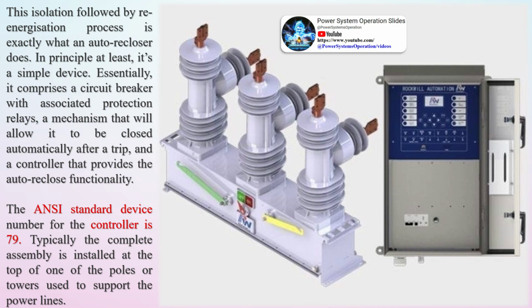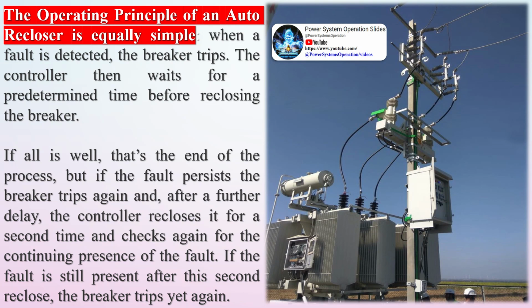If during this time a trip occurs again, the second cycle of the auto-recloser will run in case of multiple shots, or the first cycle will be completed as unsuccessful, i.e. CB opened, in case of single shot. Blocking lockout: the following conditions shall block the auto-recloser cycle: all reclosing shots have been carried out and a new fault occurred during reclaim time; the breaker is closed manually; the breaker is not prepared for reclosing; communication link failure between line protection.